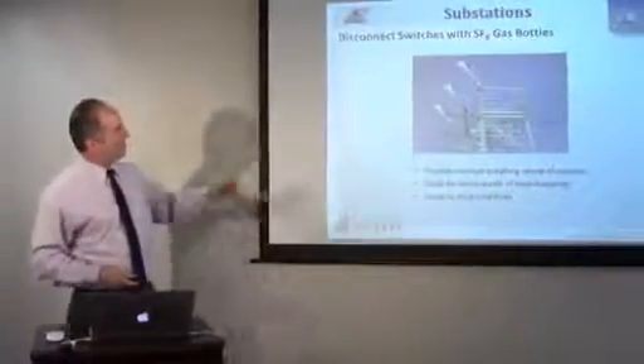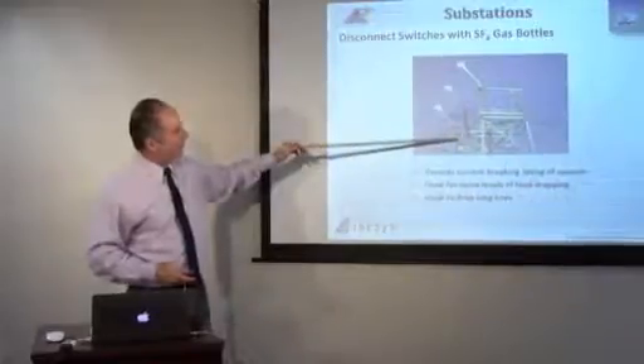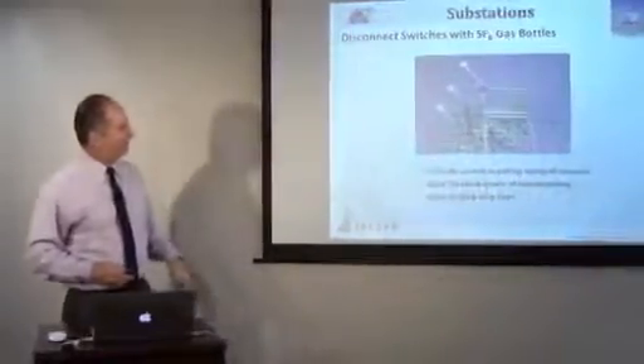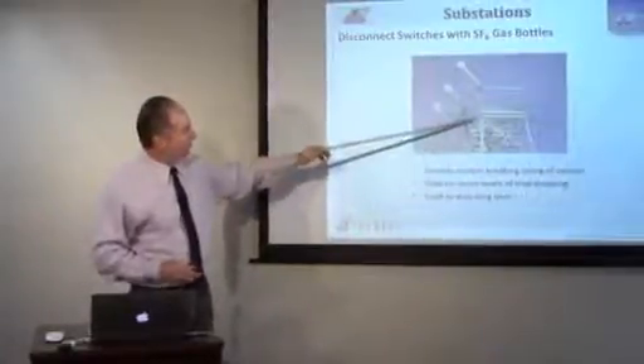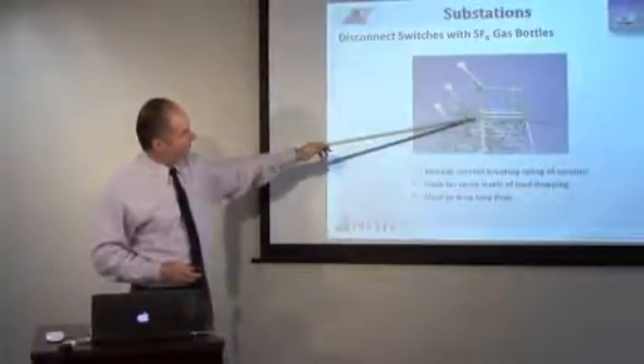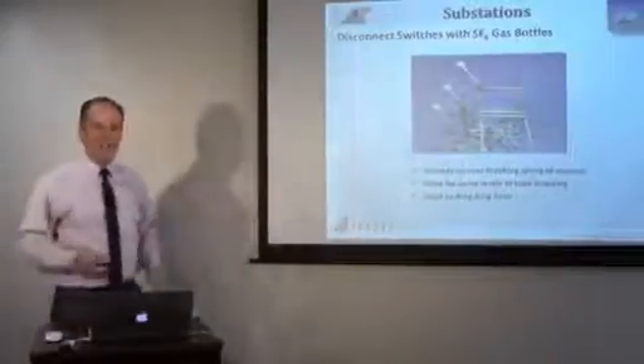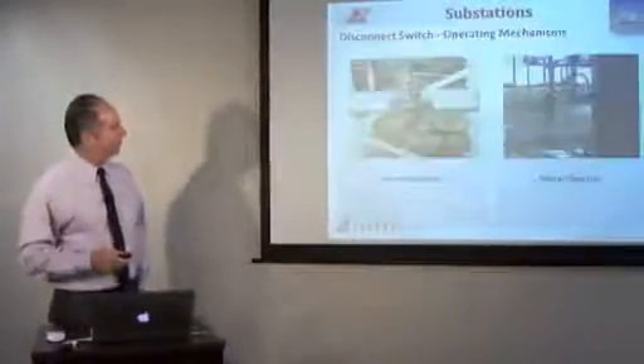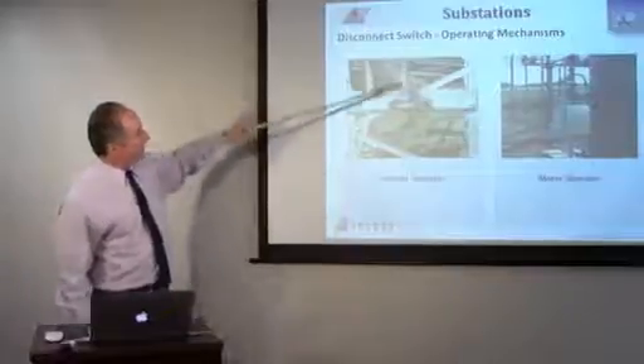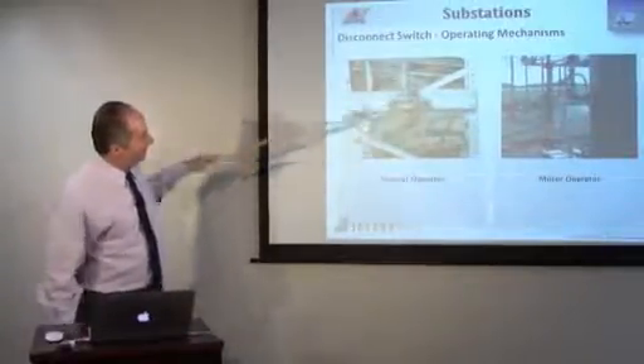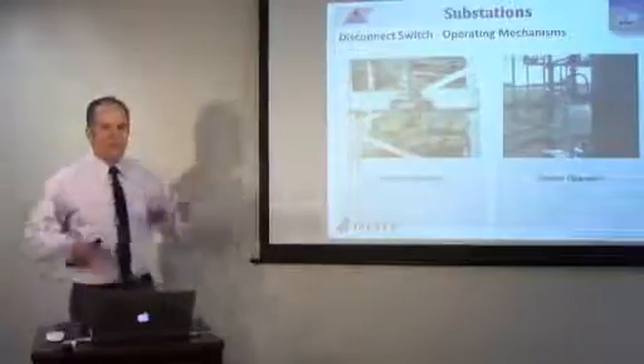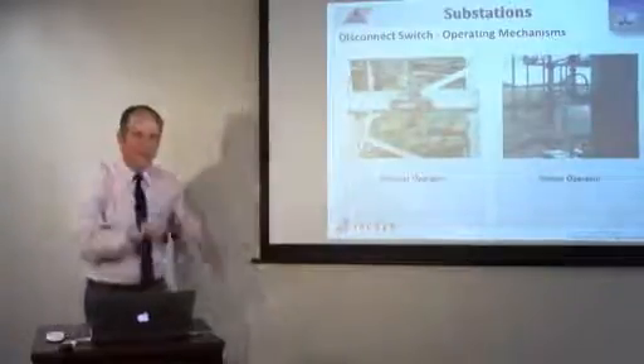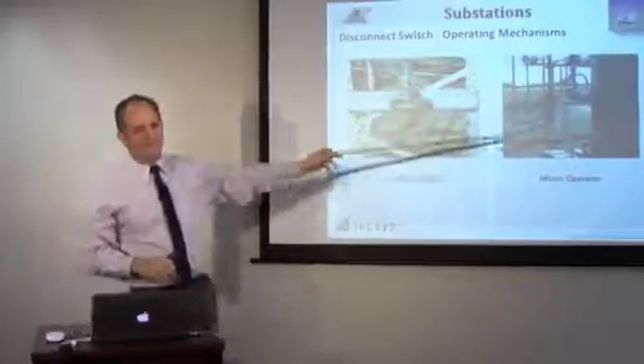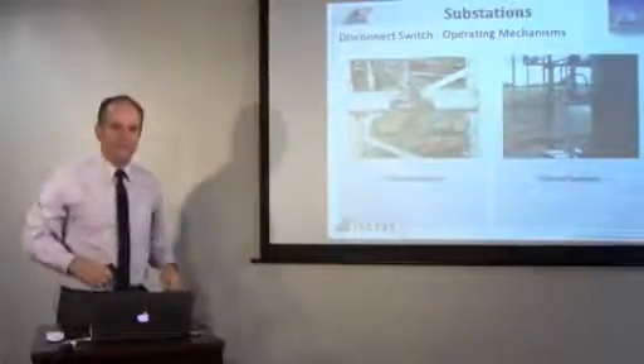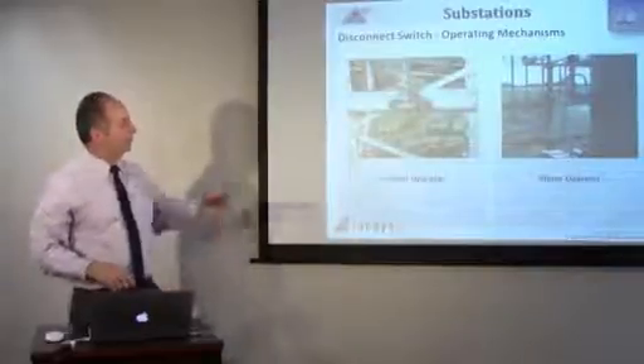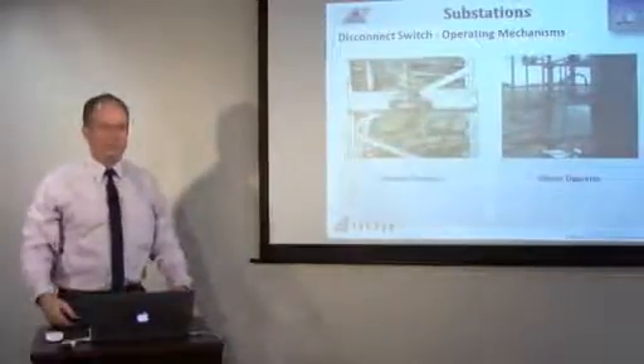Now these are gang operated, which means all three operate with the same control rod. All three switches on a common control rod operate all three at the same time. So timing is an issue. Sometimes one opens before the others, and that could be a problem. Then the rod that comes down could be hand cranked with a hand crank this way. It could be a lever this way. It could be a pull down, or it could be like in this other picture, motor operated and then controlled through system control. So you have motor operated, you have manual, different types of switches.